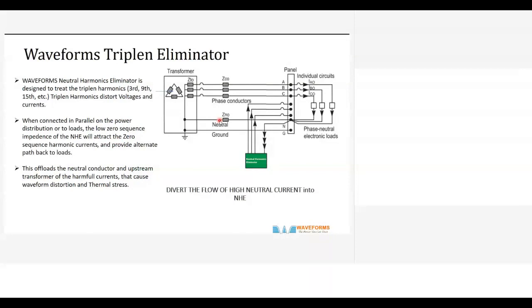The neutral harmonic eliminator is designed to treat triplen harmonics. Triple harmonics distort voltages and currents much more than other harmonics. The important thing about this filter is that it is connected in parallel, so it need not be sized to the entire load requirement. It is sufficient to take care of the neutral currents, which can sometimes be 10% or 20% of the load. So you can design it to just 10% of the load to take care of the neutral current.